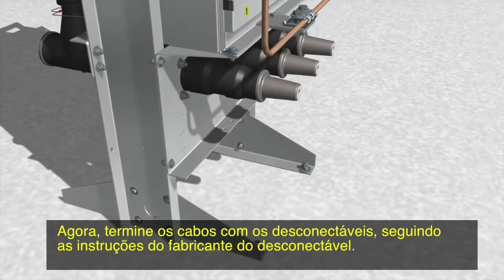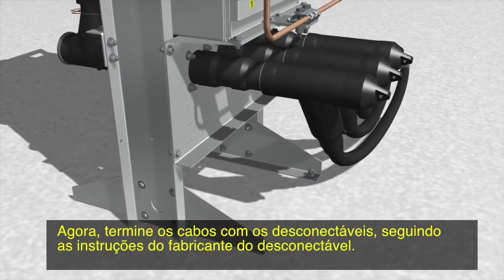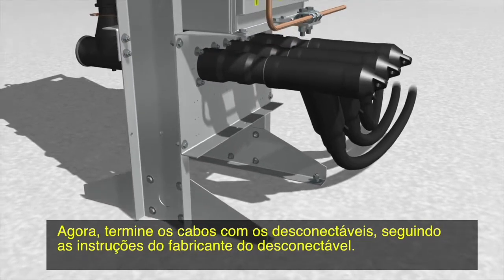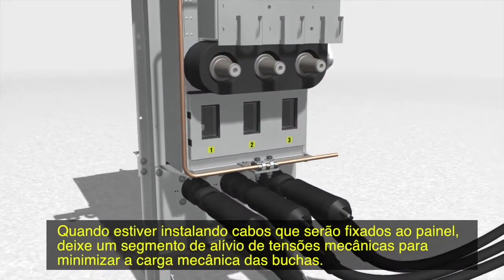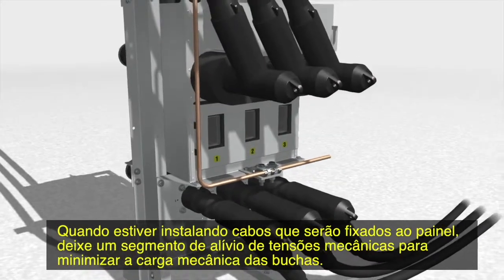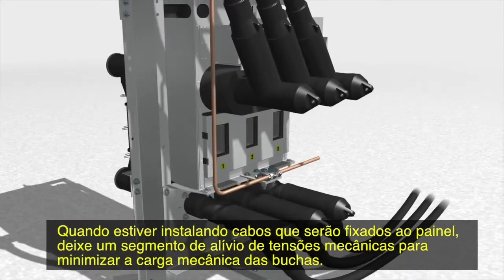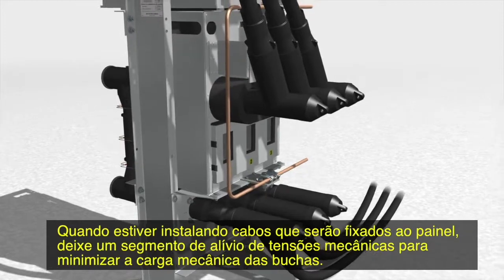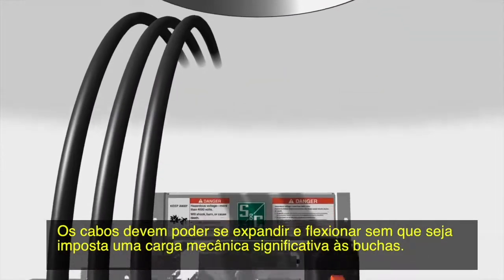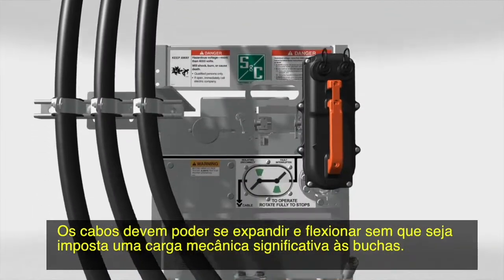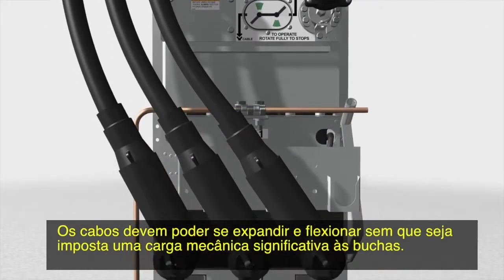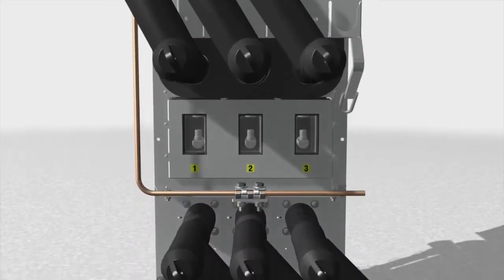Now, terminate the cables with the elbows, following the elbow manufacturer's instructions. When installing cable that will be attached to the switchgear, provide a strain relief segment to minimize the load on the bushings. Cables must be allowed to expand and flex without putting a significant load on the bushings.